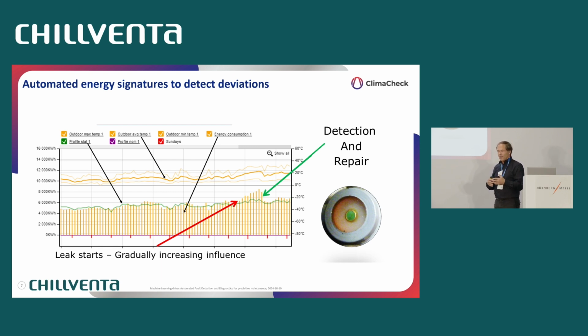One interesting application is, of course, if you build the energy signature for the plant, most plants would reflect both the performance, and the load is dependent on the outdoor temperature. So you get an energy signature that's very characteristic for that site. And if you track that, and you optimize your system, you get a nice profile, which we call the energy signature. And if your system is deviating, then it's changing something in the system. So either it's a performance change on a component level, which we have in the performance analytics, we have every component, but it could, for example, be a refrigerant leak, and that will have an impact. So you can detect, depending on the system, this might be a very good way of detecting leaks if you have a receiver. Whereas if you don't have a receiver, normally there would be other parameters that would be indicating much sooner than the...